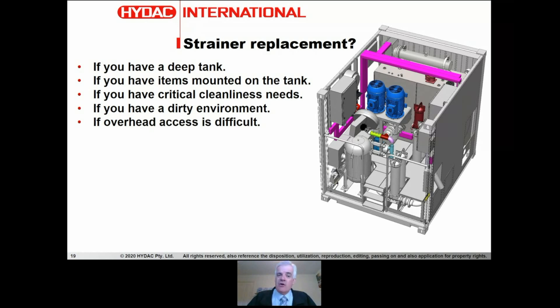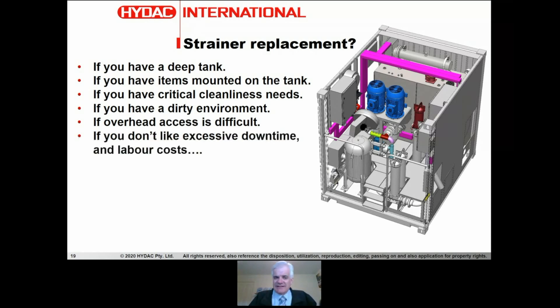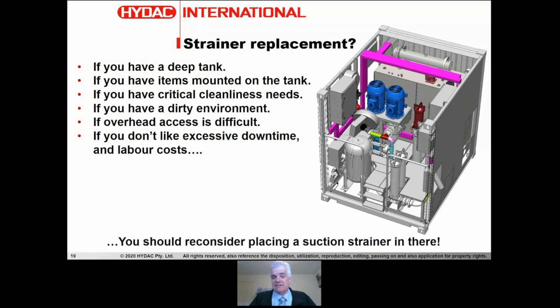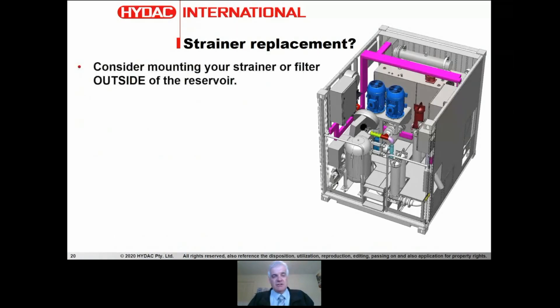In a mining or agricultural environment, you don't want anyone opening that tank if possible just to change a suction strainer. If overhead access is difficult - for example, heavy manifold blocks on the tank - or if you don't have crane access, you don't want to be opening that lid. If you want to avoid excessive downtime, excessive labor costs, and difficult jobs, you should reconsider placing a suction strainer in that reservoir. There are other ways to do filtration more effectively.